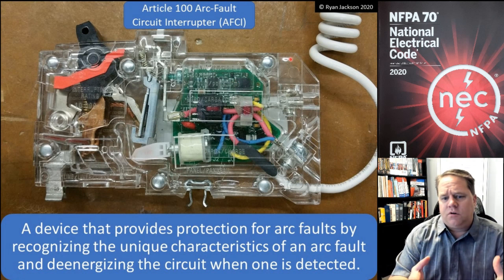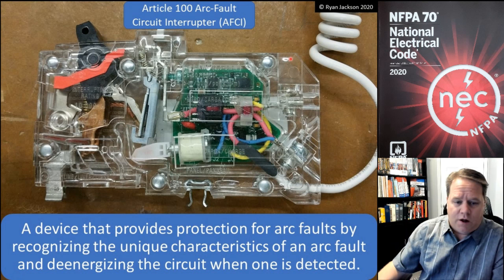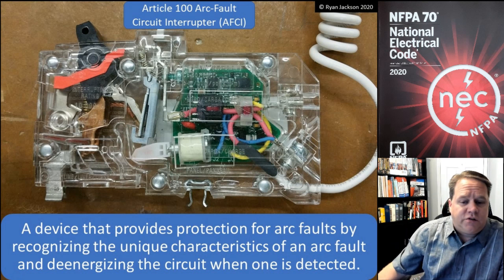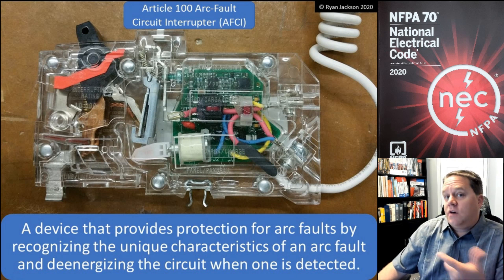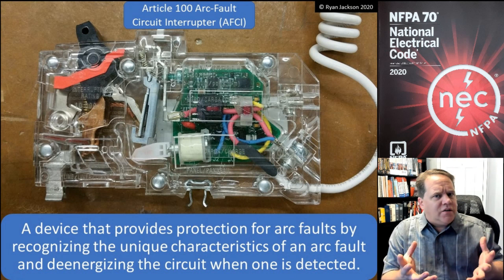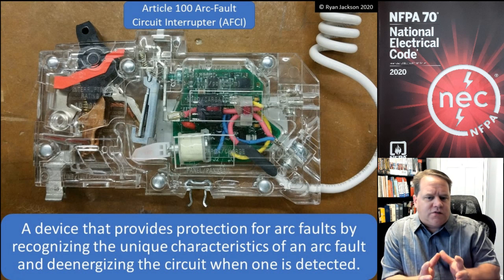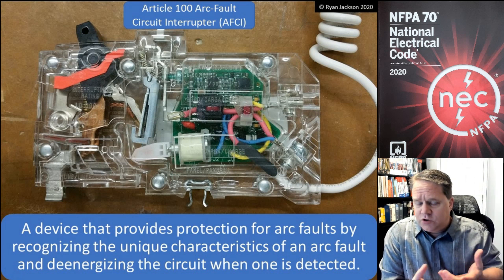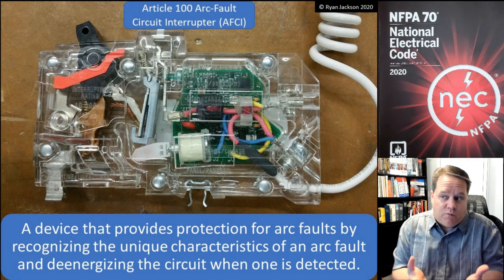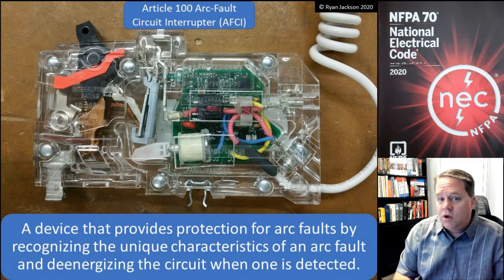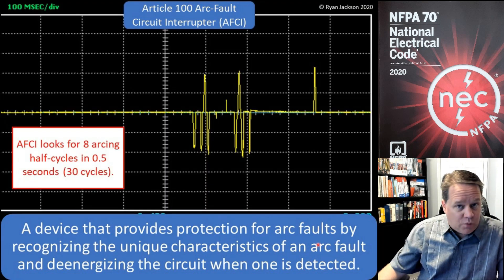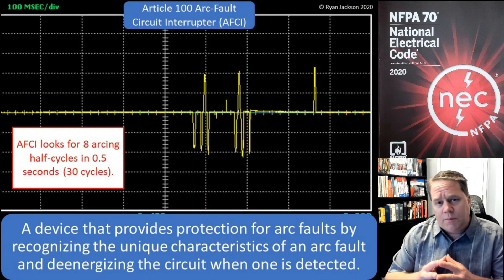What does that circuit board do? Well, it recognizes the unique characteristics of an arc fault and shuts off the circuit when it sees one. How exactly would you sense the unique characteristics associated with an arcing fault? Basically, we look at the sine wave. In an arc fault circuit interrupter there is essentially an onboard oscilloscope that reads the sine wave.